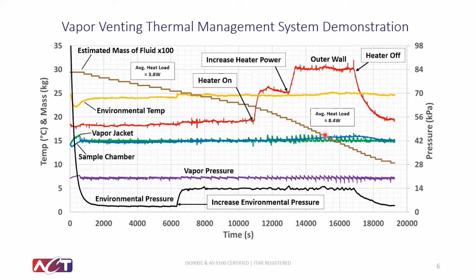So during this period of time, the average heat load was estimated to be about 8.4 watts. We can see a very slight increased temperature of the sample chamber by only about 1 degree, but ultimately this demonstrates the ability of this concept to maintain a nearly steady sample chamber temperature despite a changing thermal environment.